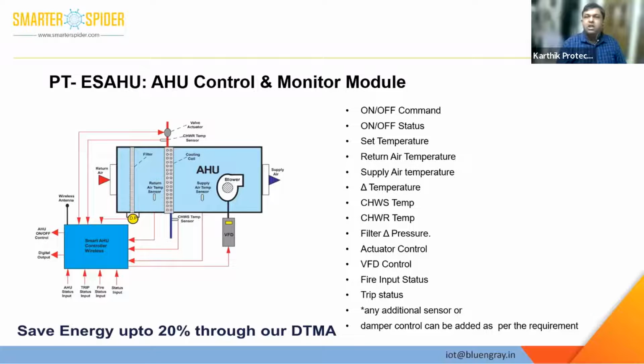another module where, with the help of the on-off status of the AHU, we can set the temperature that is required to be maintained inside the room, then measure the return air, supply air, chill water supply, chill water return, and based on these 4 parameters, we control the actuator.